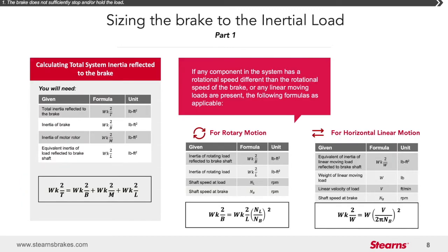For oversized motors or unique performance requirements, size the brake by factors such as inertia or stop time. The following calculations are appropriate where there is high inertia in critical applications, as well as many overhauling load conditions that require both stopping and holding torque. In this first formula, total system inertia reflected to the brake is equal to total inertia of the brake itself plus inertia of the motor plus the equivalent load inertia reflected to the shaft going into the brake, where inertia is represented as pound-feet squared.